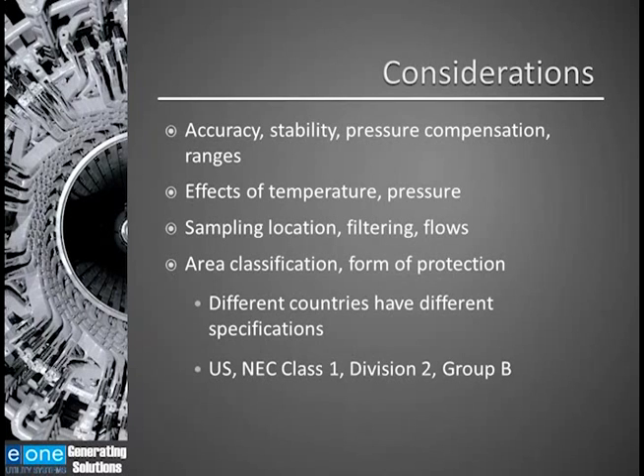Here are some considerations, some of them the same as when you're purchasing or speccing out a hydrogen analyzer or gas analyzer. You want it to be accurate, obviously. Again, you want it to be stable. You don't want to have to recalibrate this piece of equipment all the time. You want to make sure that the pressure is being compensated for, because a change in pressure will affect the dew point reading. You want to make sure that the monitor covers the range that you're looking for. As I mentioned earlier, a good alarm point is 0. You want to make sure that your hydrogen dew point is lower than 0. So a good range may be plus 40 degrees to negative 60 degrees. You want to make sure that the effects of temperature and pressure have little effect on the reading of the dew point sensor.